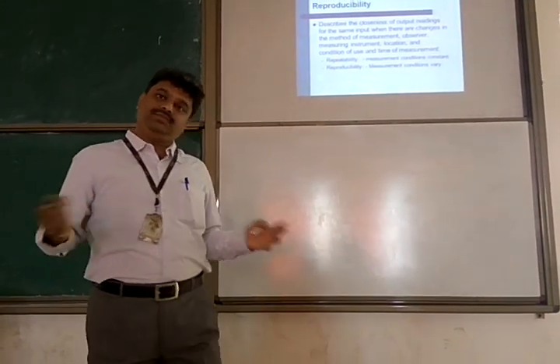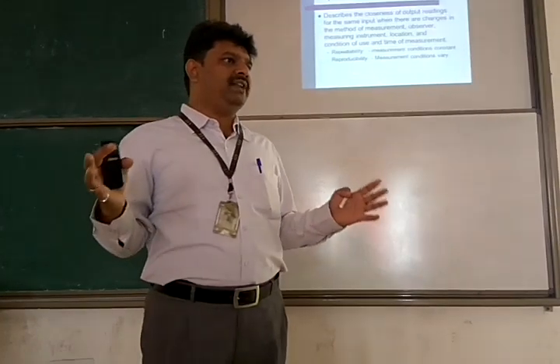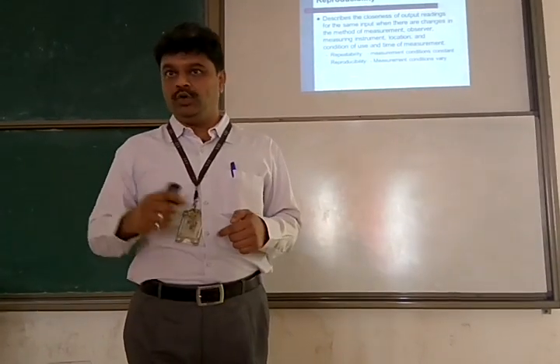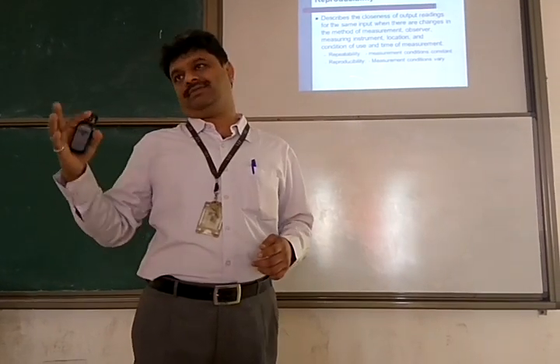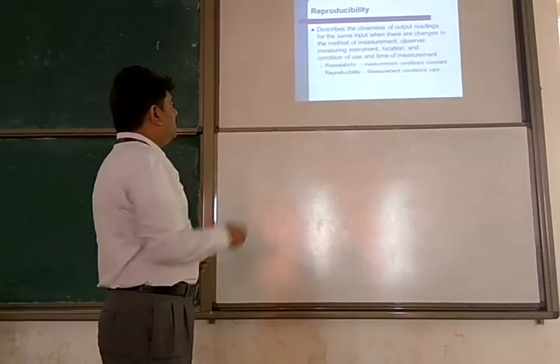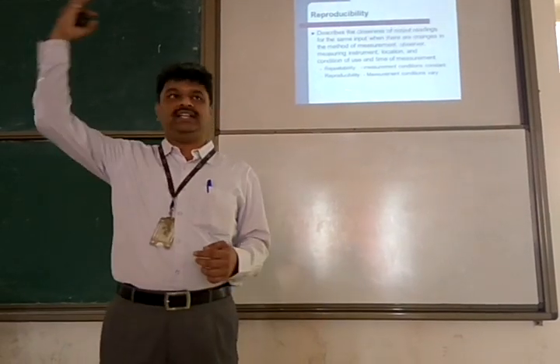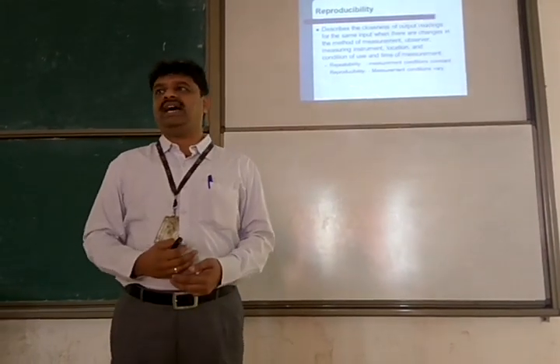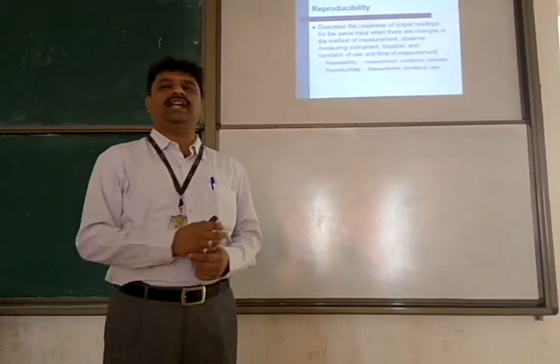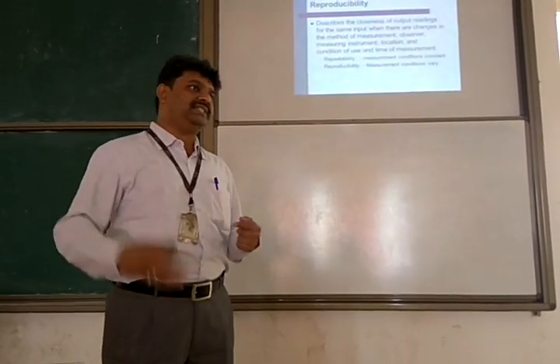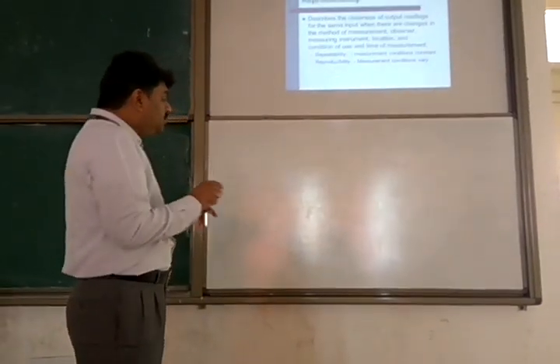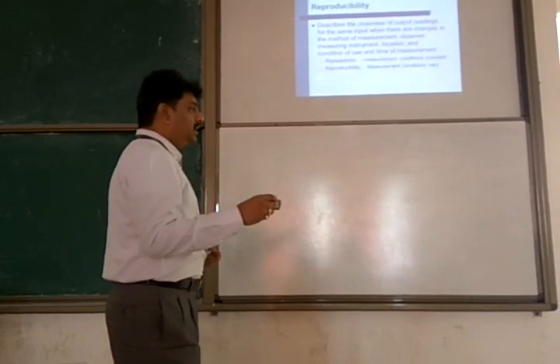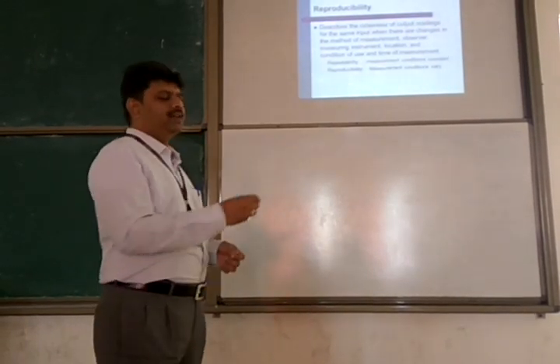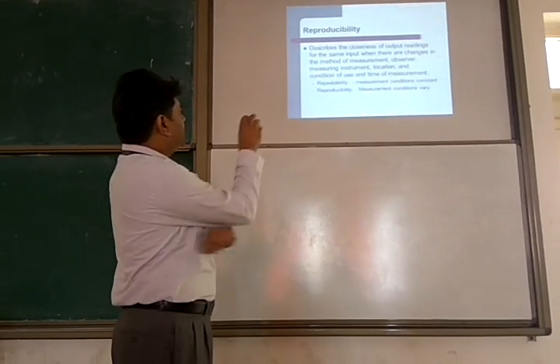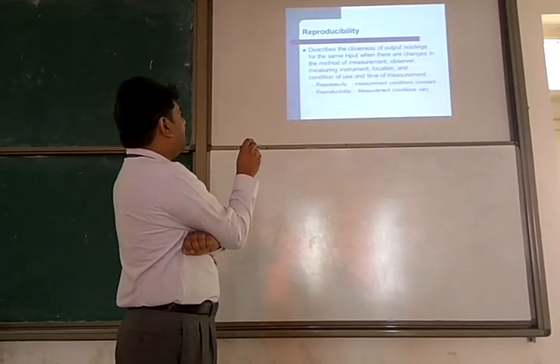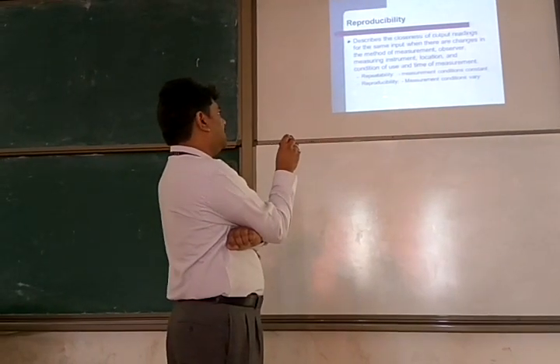Reproducibility is for versatile conditions—wherever you go, the repeatability should be good, and then you call that reproducible: you'll be able to reproduce that precision anywhere. For example, whether you take a reading from the first floor or the 8th floor of this building, you should get the same reading, because pressure up there is slightly less than on the ground floor, and gravitational force also changes slightly as you go up. No such variation should affect the accuracy of the reading. Such calculations done under controlled conditions, you call repeatability.